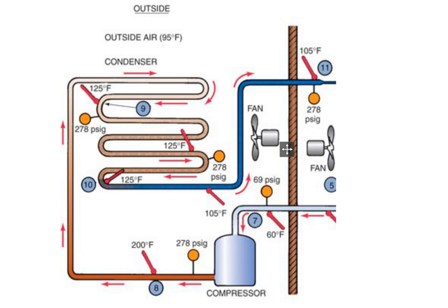Now is when you have to remember what saturation means, and that means when the refrigerant is in both its liquid and vapor state. If you add heat, it changes from liquid to vapor. If you remove heat, it changes from vapor back to liquid. So in the refrigeration cycle, on the condensing side, coming out of the compressor, we have 100% vapor coming out. So we're not saturated at this point. It is superheated vapor only. And the pressure temperature chart only refers to refrigerant at the saturation point. So right here, it's not at the saturation point. It is 100% vapor, and it is being de-superheated.